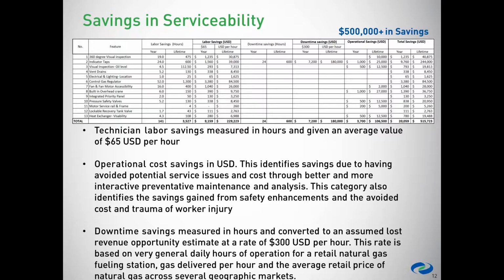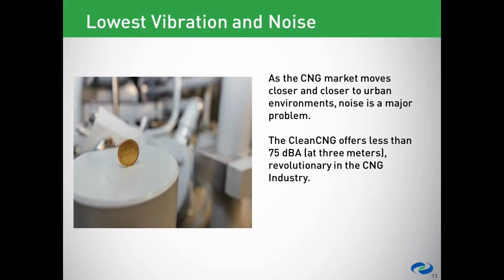As mentioned earlier, the new package has a much lower design noise level compared to some of the previous packages. Testing on one 250 horsepower package here at the factory showed that we were able to achieve lower than 75 decibels A-weighted at 3 meters, which is very low, and particularly compared to some of our previous designs and many of our competitors.